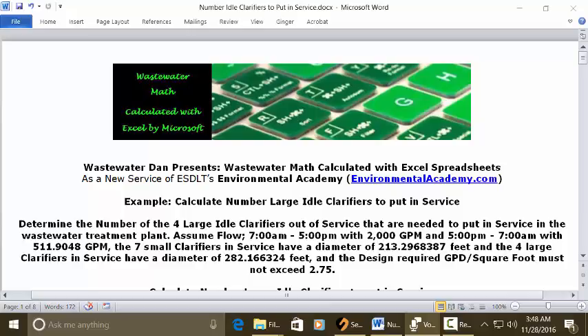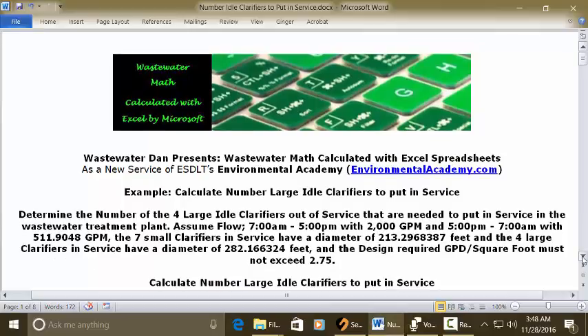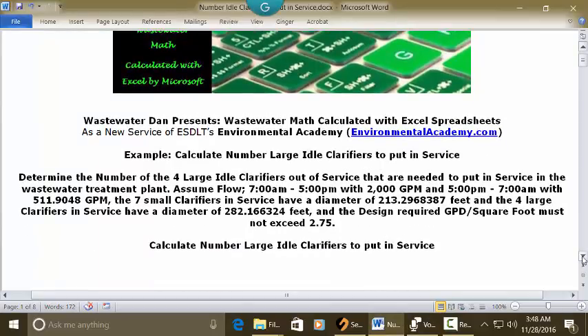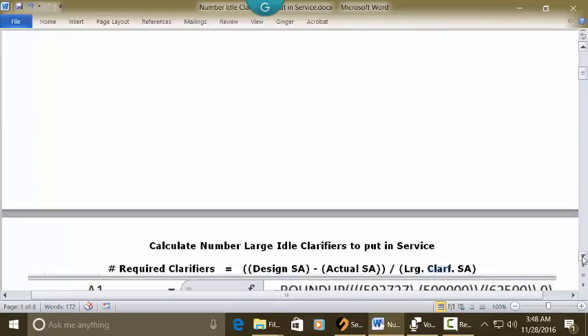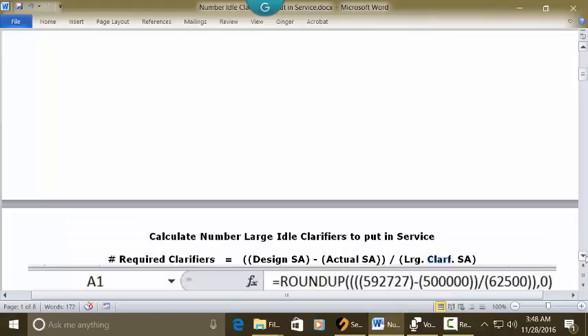The design required GPD per square foot must not exceed 2.75. We're going to calculate the number of clarifiers required by taking the surface area required based upon the design criteria, minus the surface area that's actually in service, then dividing by the surface area of the large clarifier.